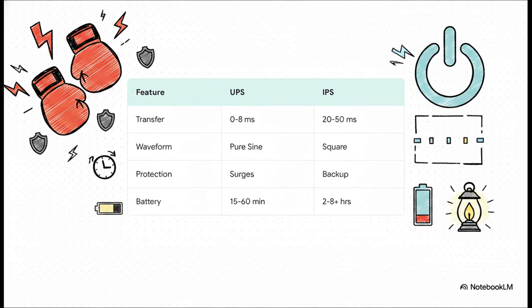In the UPS corner, you have precise, rapid protection. Transfer time is an undetectable 0 to 8 milliseconds. It offers comprehensive protection against surges, spikes, and electrical noise. But it burns out fast, typically providing only 15 to 60 minutes of battery life to let you safely shut down servers or fire up a backup generator.